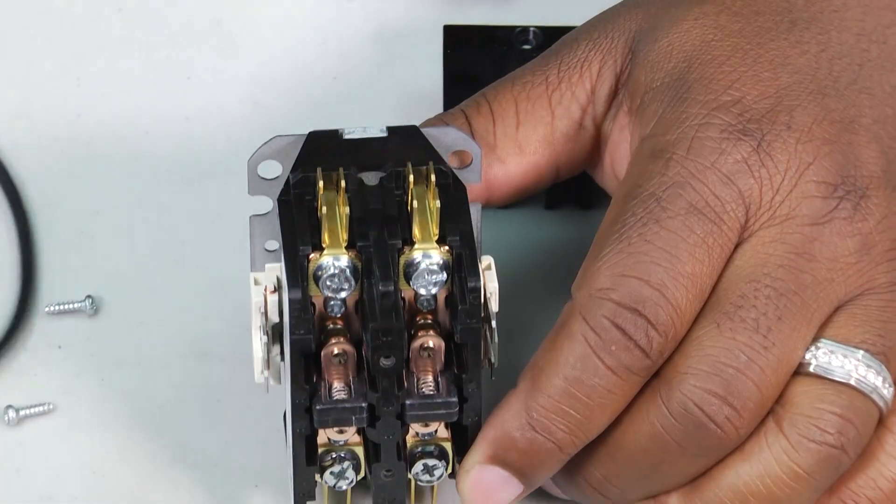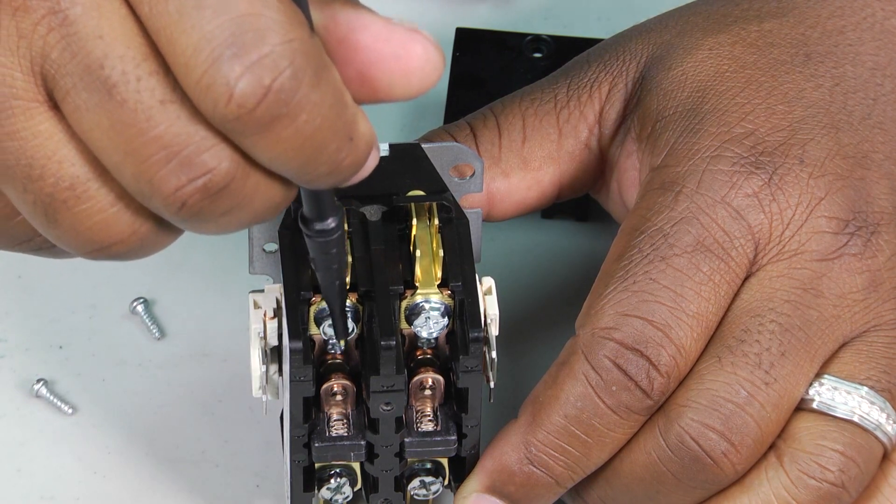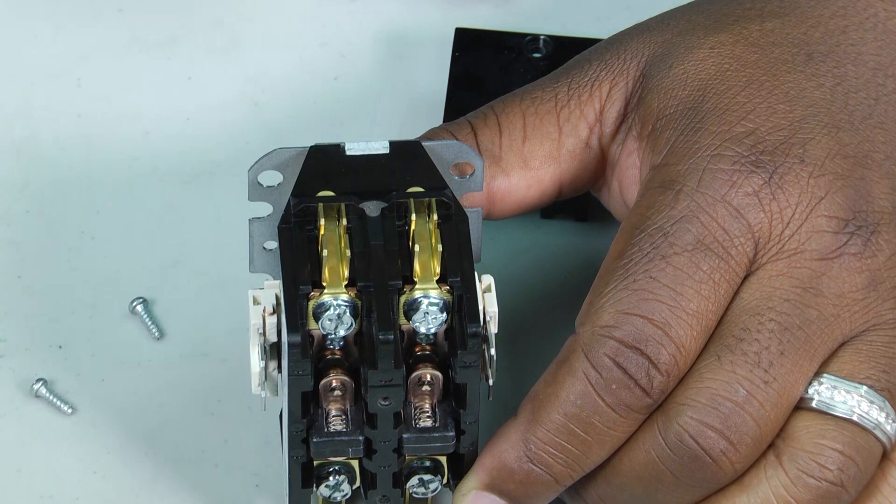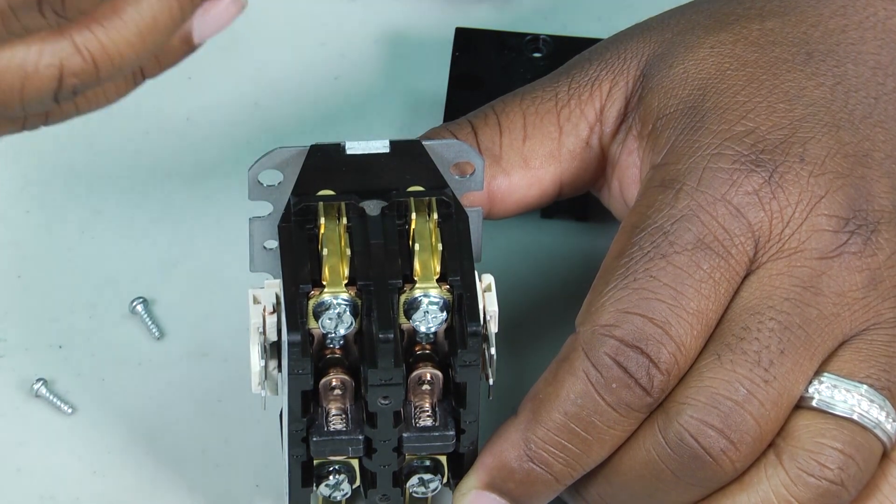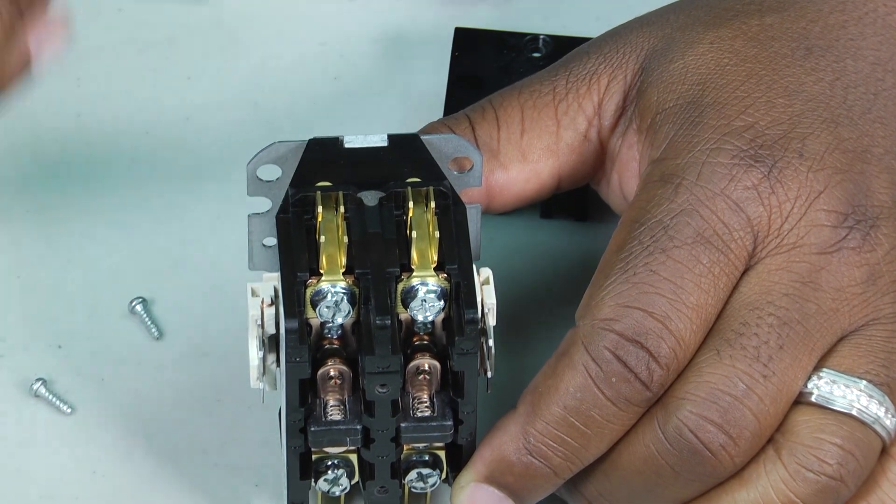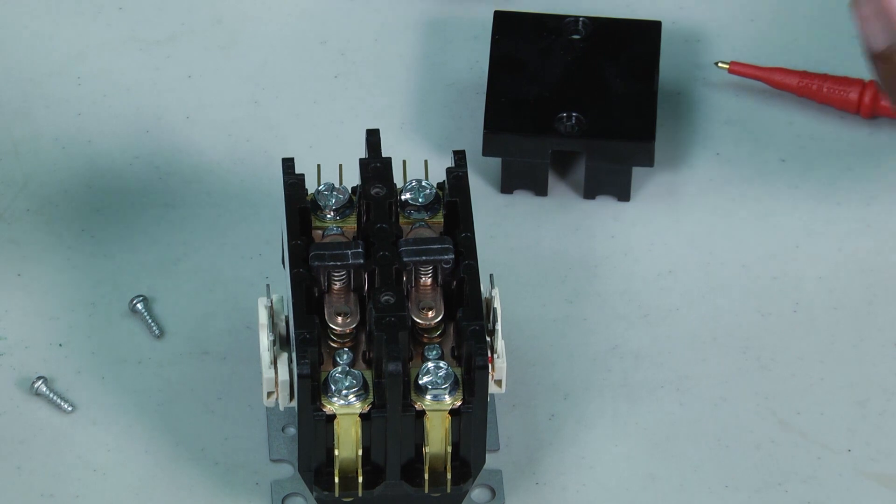When that arcing happens, if you look down inside, those contact plates either won't make connection for the electricity to pass through, or they'll be welded shut and the system just runs. You can't shut it off. That's one of the issues that happens, and probably one of the most common ones.